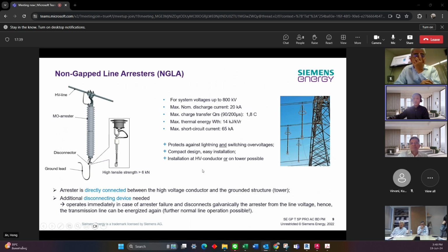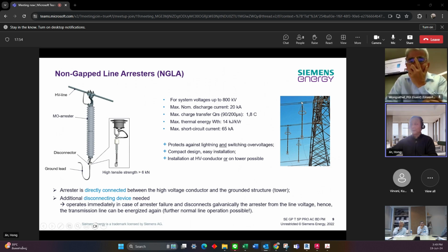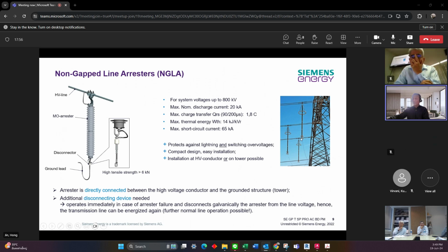So this is non-gapped surge arresters. Non-gapped surge arrestor, which means you have constant voltage applying on both ends. One is from the high voltage. Yeah. If you see the right side of the picture, this is hanging on the transmission line, a 500 kV non-gapped surge arrestor. And another side of the surge arrestor will be connected to the tower body, the grounding point. Yeah. So it will protect the insulator here. If you see, this is the insulator for the transmission line.